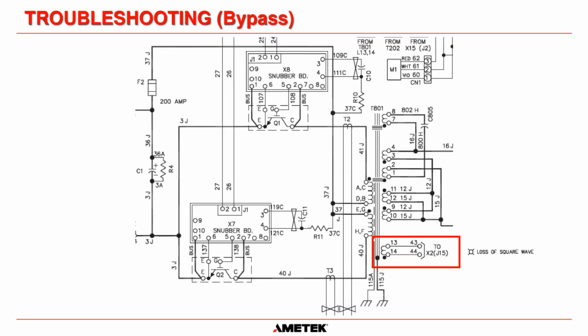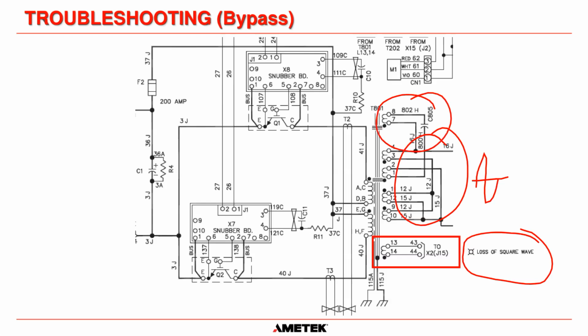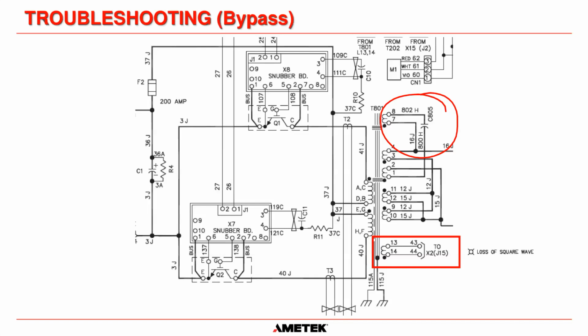Now, if the inverter is running, but it has transferred to bypass, there is this little circuit here, and it's called loss of square wave. Basically, the secondary of the transformer here is where your sine wave is coming out. And there is some stored energy, surprisingly, in this secondary of the transformer. So if we have a fault in the inverter bridge, you'll actually get about 1.5 cycles of AC out after. Is it 1.5 cycles or 1 cycle? I can't remember. But you will get at least a cycle of power from this tank circuit here and the inductance in the transformer if this side fails.